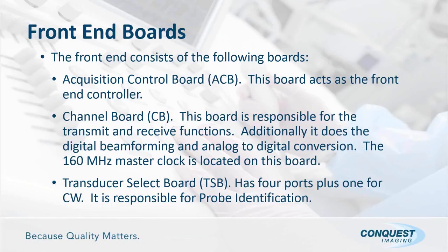Once it's amplified and time gain compensated, it does what they call digital beamforming, which is in reality analog to digital conversion and what we call summation. It takes these 128 signals that have been digitized and sums them into one large signal that can be passed to the back end. So that's what digital beamforming consists of in general terms. Then we go on to mention that it has a 160 megahertz master clock. And why do I mention this? Master clocks are pretty reliable as a norm. But what I find is, say your system's hesitating, it's freezing, it's shutting down, it's all over the place, unreliable, but it's intermittent.